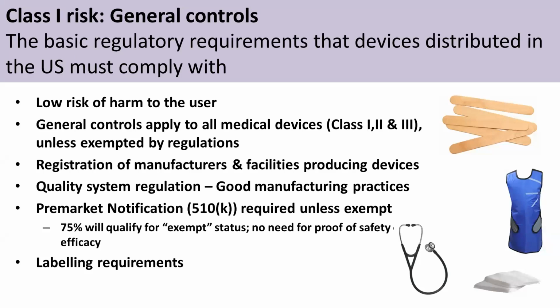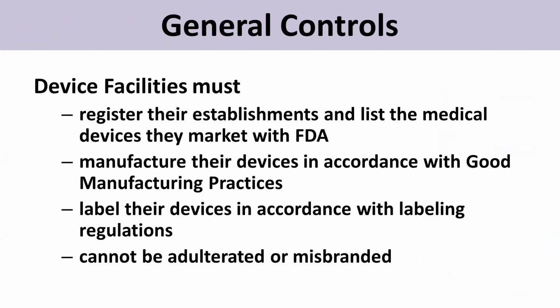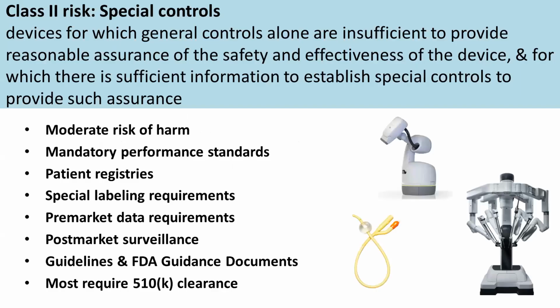So class 1 risk is subject to what are called general controls. And these are the basic regulatory requirements that any device in the US must comply with. And if you only have general controls, it's usually because there is a low risk of harm to the user. And general controls do apply to all 3 levels, but class 1 only needs this particular control. Now, companies still have to follow good manufacturing practices. They have to register their manufacturing establishments and label their devices accordingly. So the FDA is still keeping an eye on them.